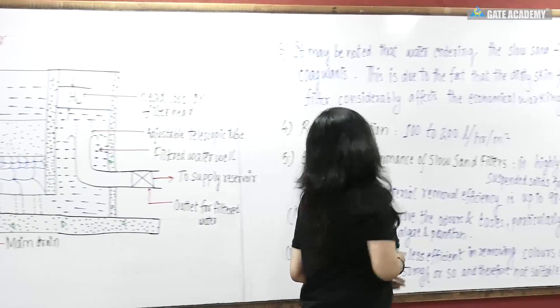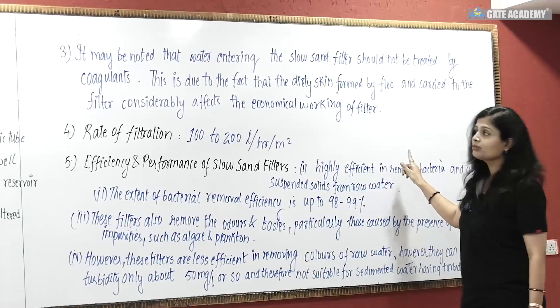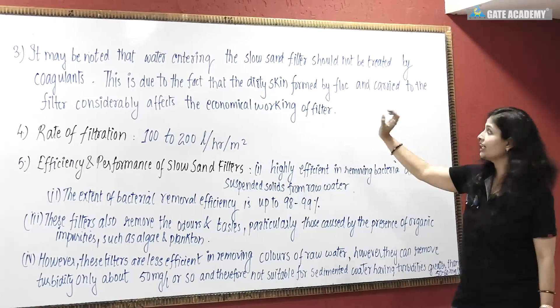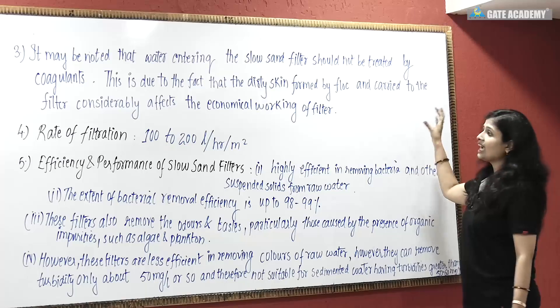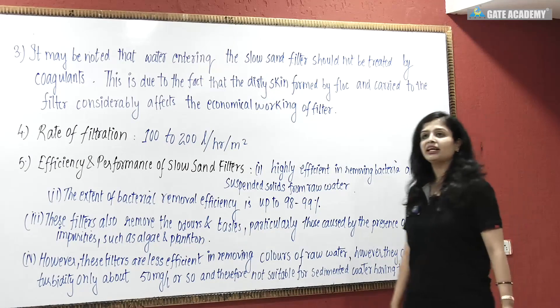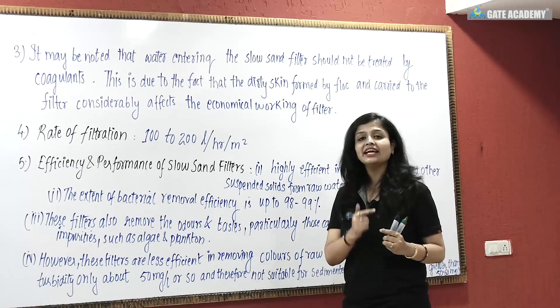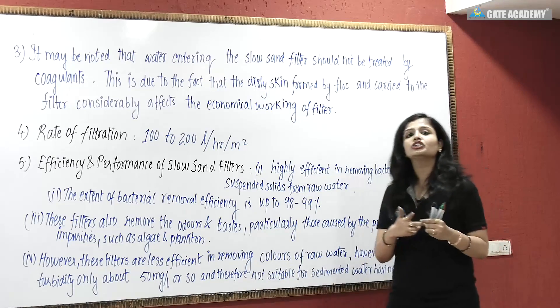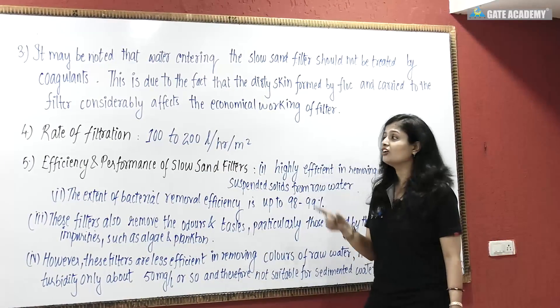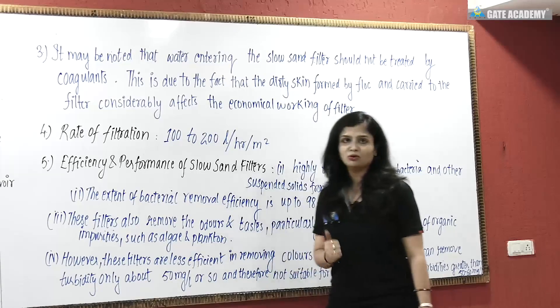It may be noted that the water entering the slow sand filter should not be treated with coagulant. This is because the dirty skin, or schmutzdecke, formed by the flocs carried to the filter affects the economical working of the filter. The rate of filtration is reduced in slow sand filters compared to rapid sand gravity filters — this is one of the main reasons we cannot always use them, and the tank area required is also increased. The rate of filtration is only 100 to 200 liters per hour per meter square.